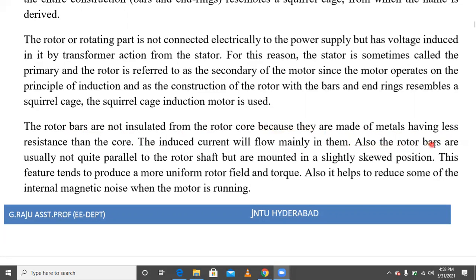Also, the rotor bars are usually not quite parallel to the rotor shaft, but are mounted in a slightly skewed position. This feature tends to produce a more uniform rotating rotor field and torque. It also helps to reduce some of the internal magnetic noise when the motor is running. So that is some concept regarding the squirrel cage induction motor.